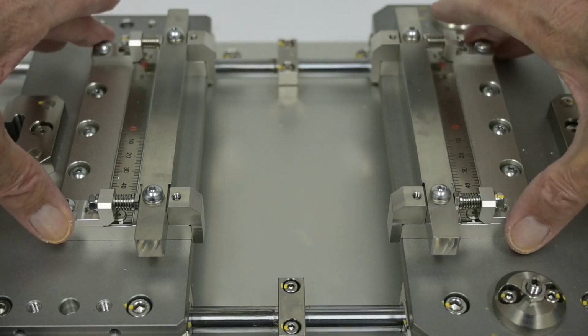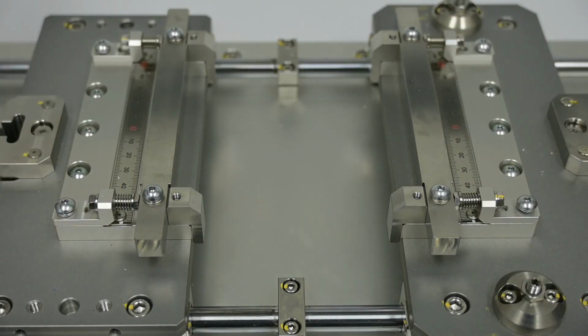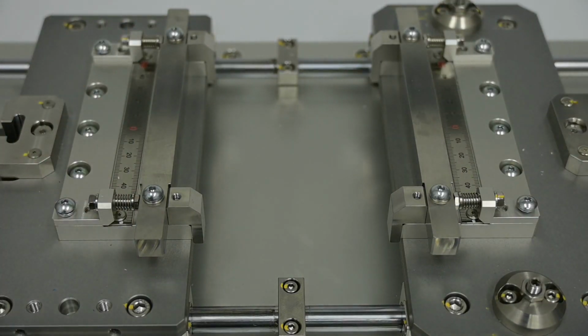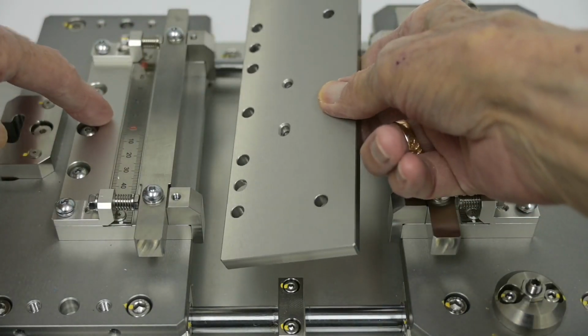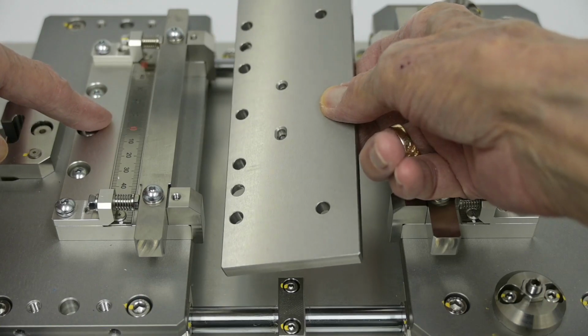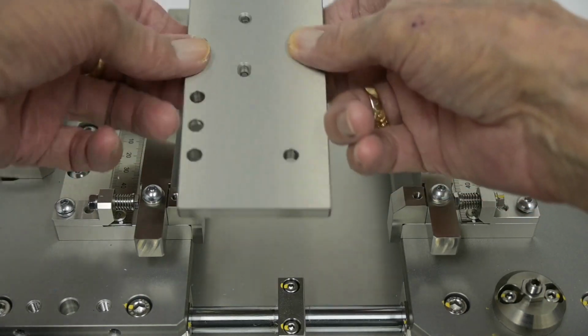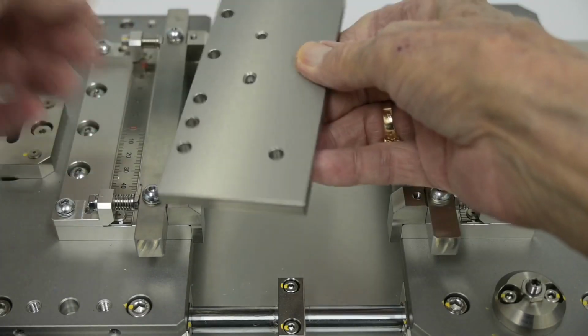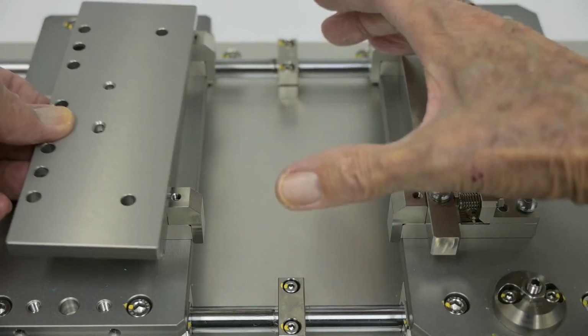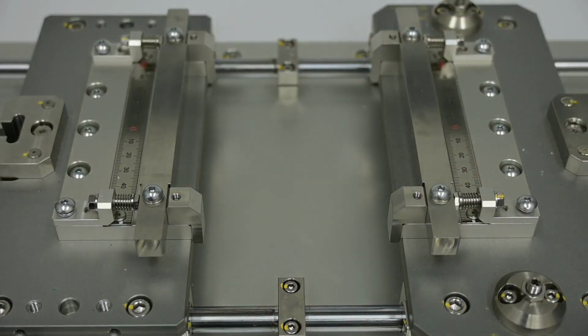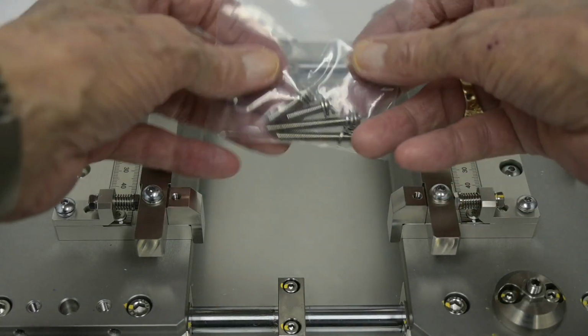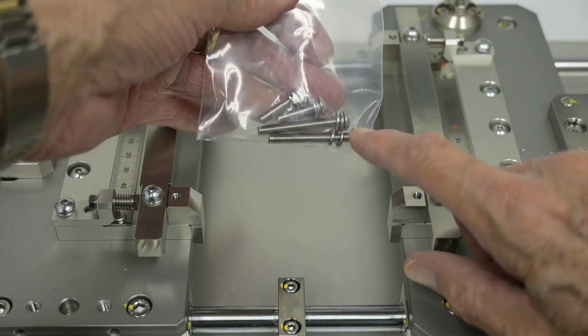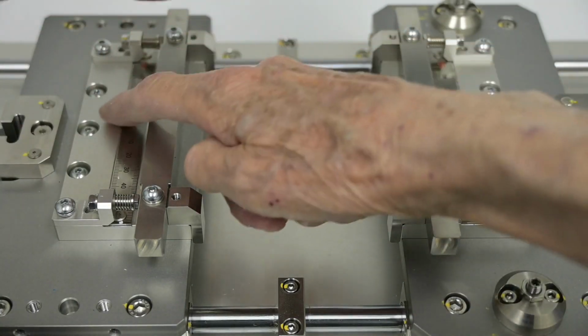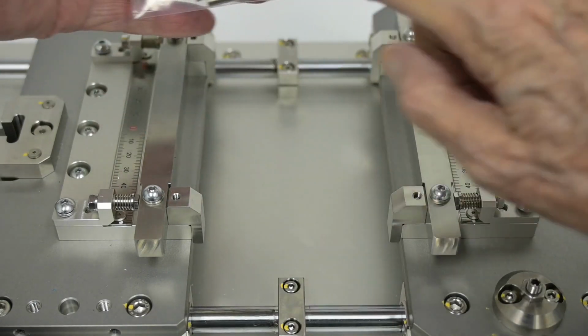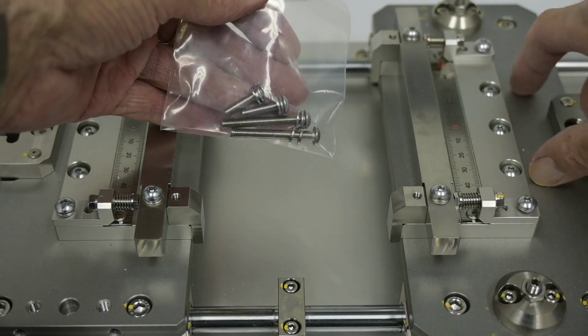These are the clamps. We will remove both of them. The moving clamp has to be raised to match the increased height of the load cell clamp. The spacer has pins on the bottom to properly align it. We will remove the clamp and install the spacer. Then replace the clamp on top of the spacer. There are 4 screws with flat washers and lock washers. 2 short ones will hold the spacer down. 2 long ones will hold the load cell clamp down.